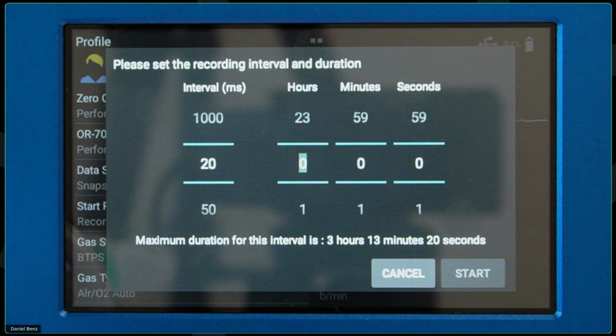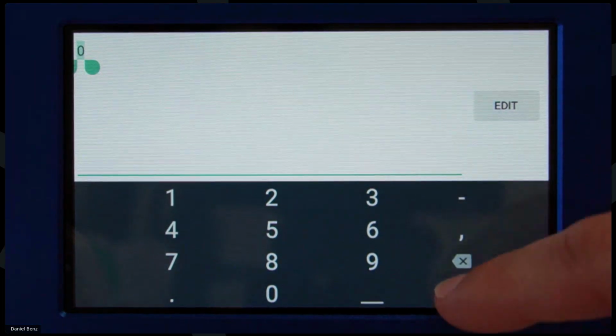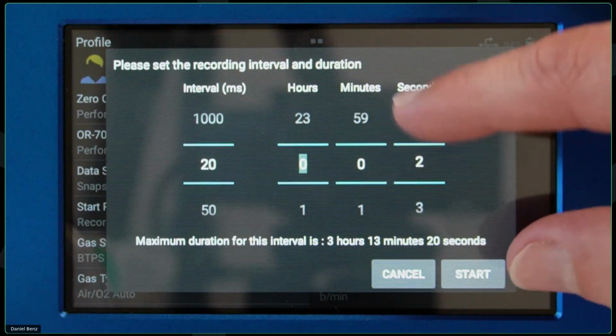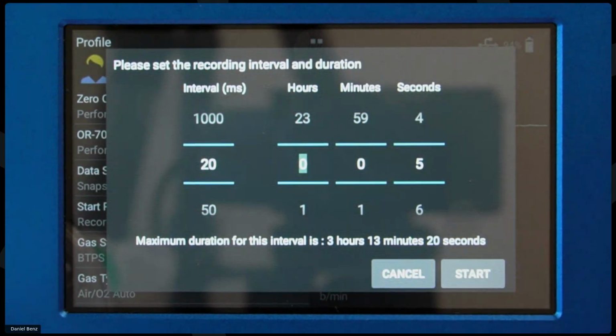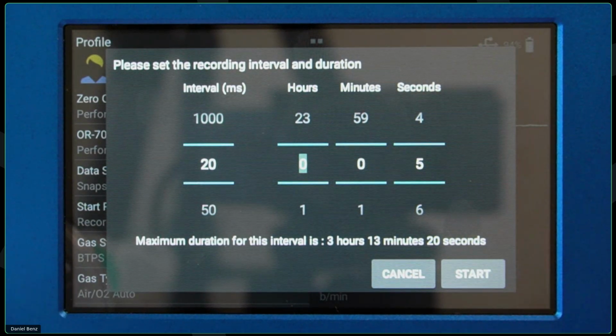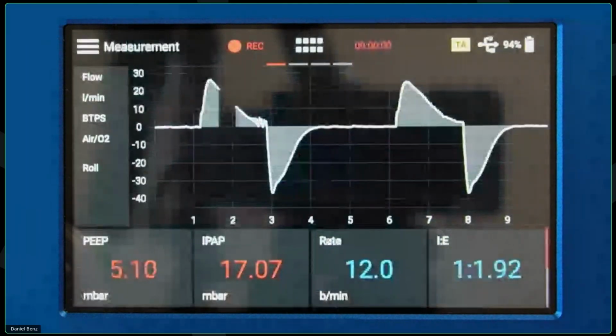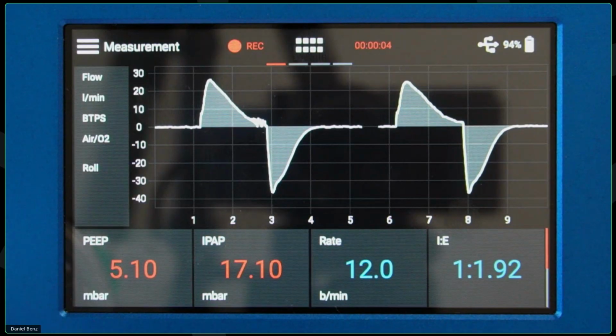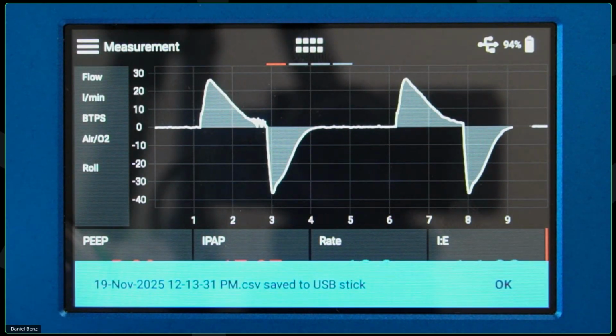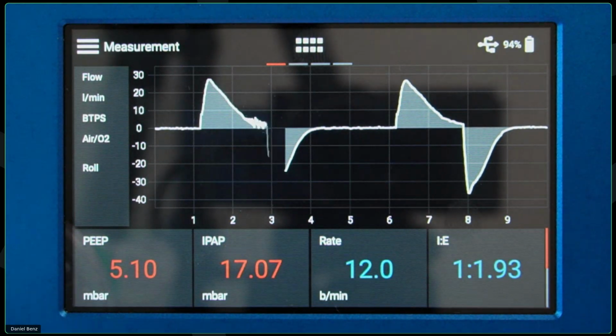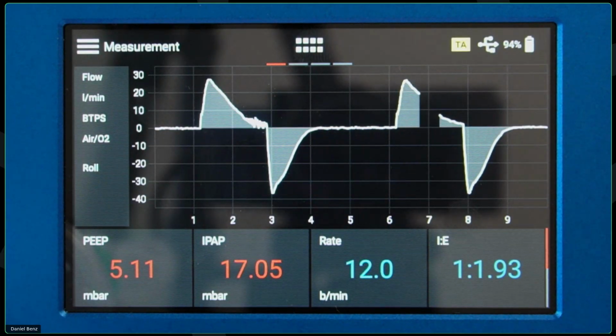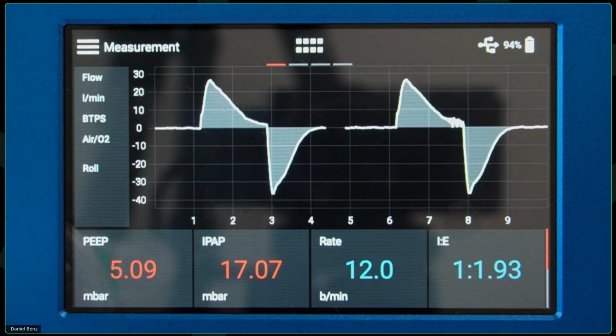So first of all, I can set my recording interval. I can go back down to 20 milliseconds. That's going to be the resolution of my measurements, so my sampling rate. And then I can set the duration here. Let's do 5 seconds for this, but you can record up to 24 hours on the device, and then hit start. And now you can see it indicated up here. It's recording all the values over time into a CSV file that is being saved on a USB pen drive connected to the device. So this is very convenient. Afterwards, you can analyze this file, for example, in Microsoft Excel. It's just a CSV file that you can then get from the USB pen drive.